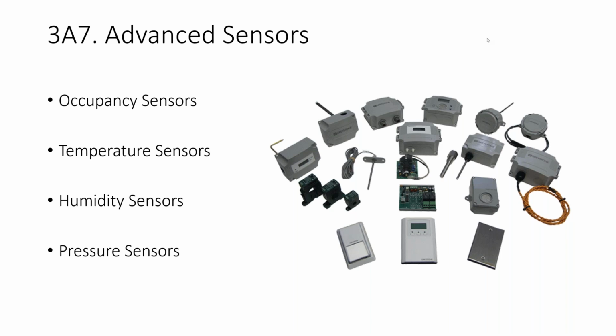These sensors increase our efficiency in a way that, in spaces where we need scheduled heating, in every single space there are thermostats which send the temperature back to the control room, and that's how we control the temperature of the space. And in the main air handling units, the sensors are used to check humidity and air temperature, for example if we are sending really cold air, which is not efficient because we are reheating our supply air close to the space, as in a reheat system. So those sensors help to run our systems efficiently.